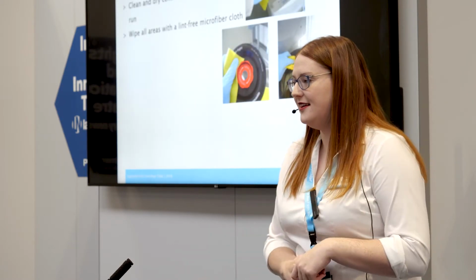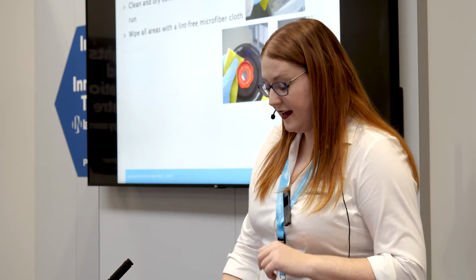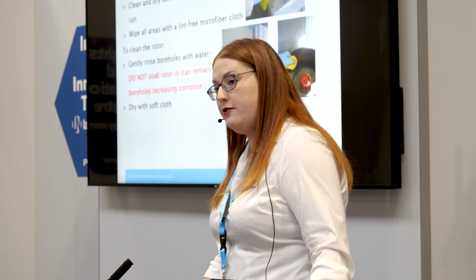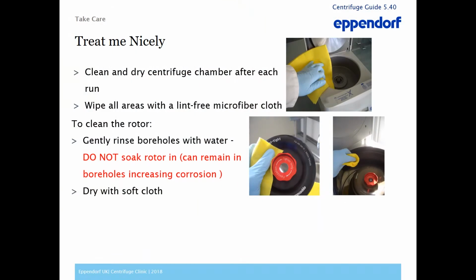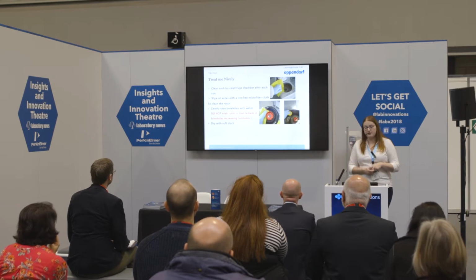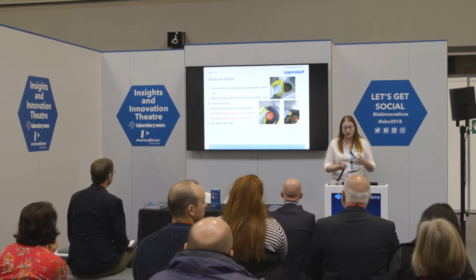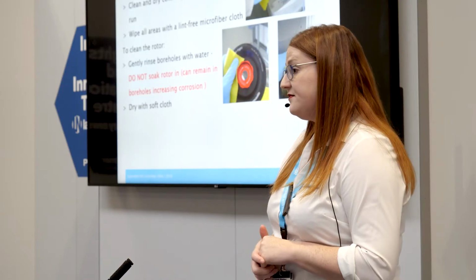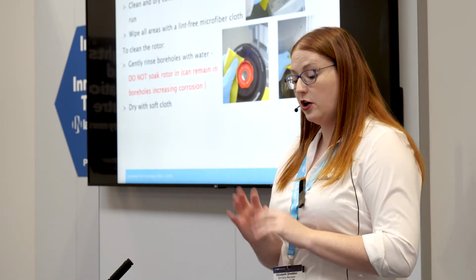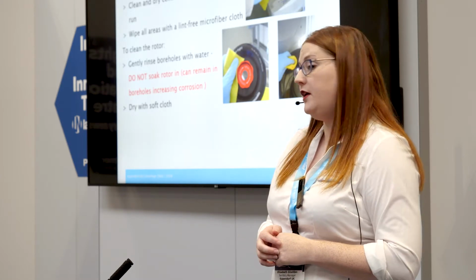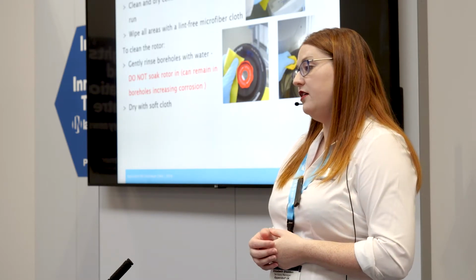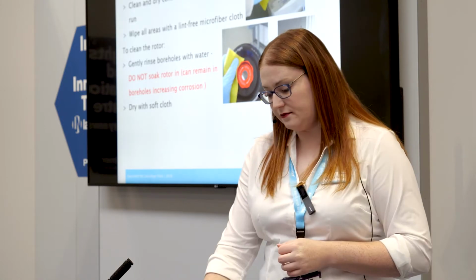So, actually clean them and dry them. We say after every run, but certainly after a refrigerated one, when you're going to start to get condensation building up in the rotor, wipe the water away. Okay? Preferably with a lint-free microfiber cloth that isn't going to get into the mechanism and start causing any problems. If you do need to actively clean your rotors, you can run them underwater and fill the boreholes, but don't soak it, and dry them. Don't just leave them, actually dry them, because the water, again, will just slowly corrode your rotors.